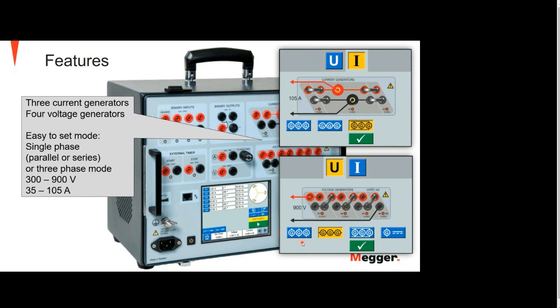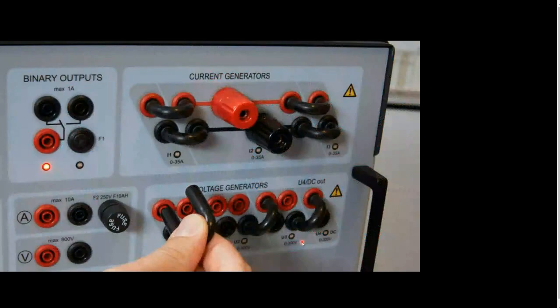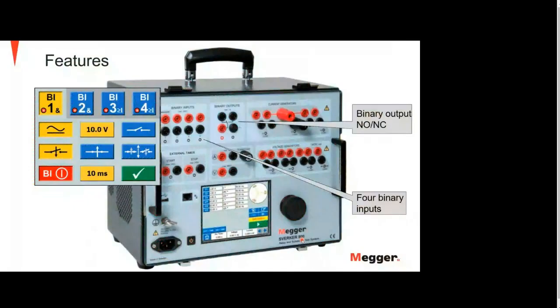Practically, when you're changing from series mode to parallel or individual mode, you're using the jumpers, which come together with the Sverker 900. We also have 4 binary inputs and 2 binary outputs, normally open, normally closed. They could be used for simulating a breaker, for example, when testing auto reclosing.